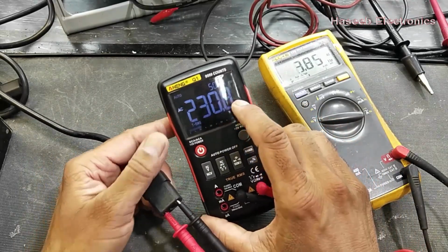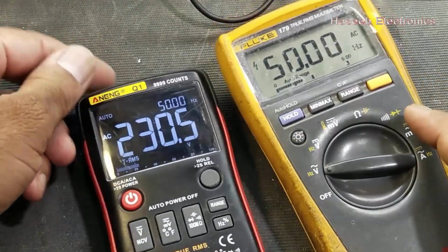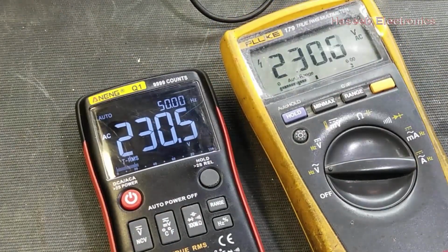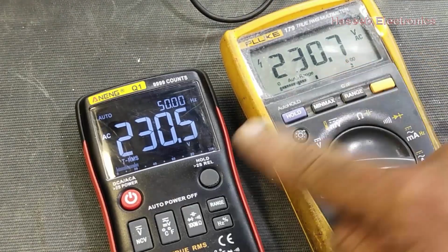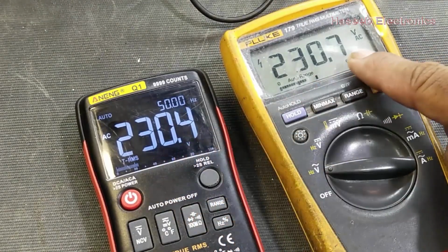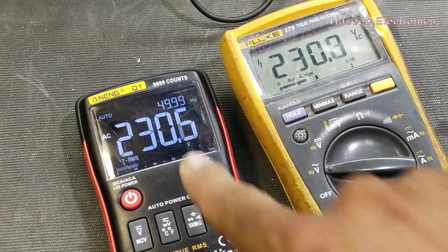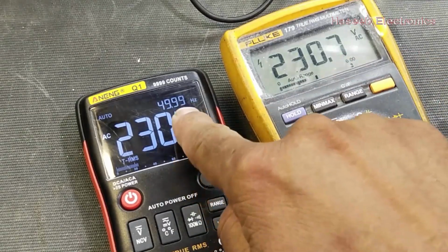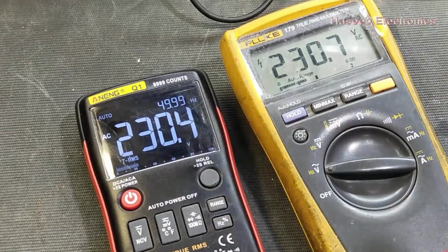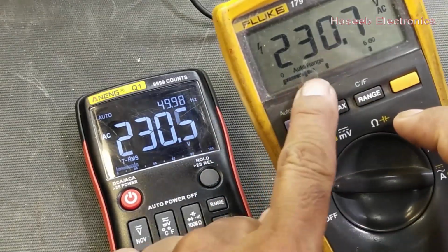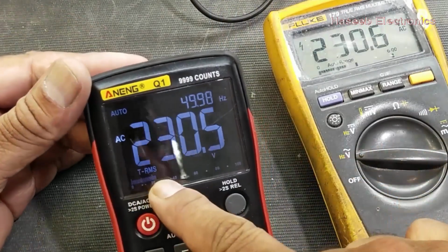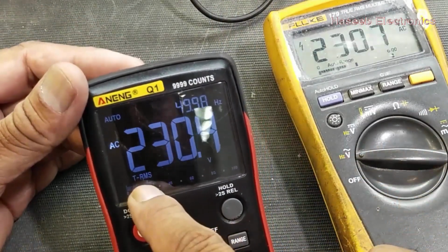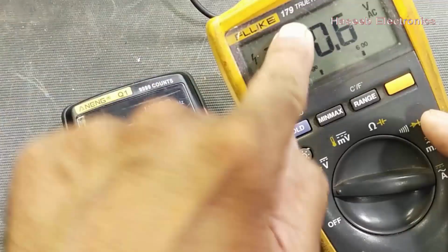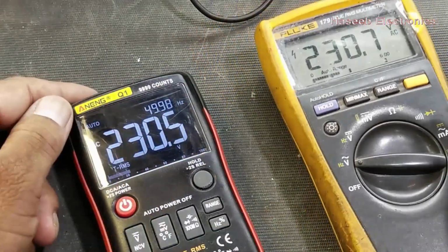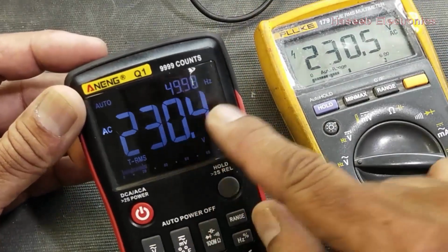Yes, it is giving 50 hertz, 50.01 hertz. So the frequency is the same. And 230.7 volt, 230.5 volt. So both readings are nice. Here we have an additional thing, that we have secondary measurement here. We have a bar graph here, and we also have an analog bar graph here, and here it displays true RMS. This multimeter is also true RMS, so it displays that these voltages are true RMS.